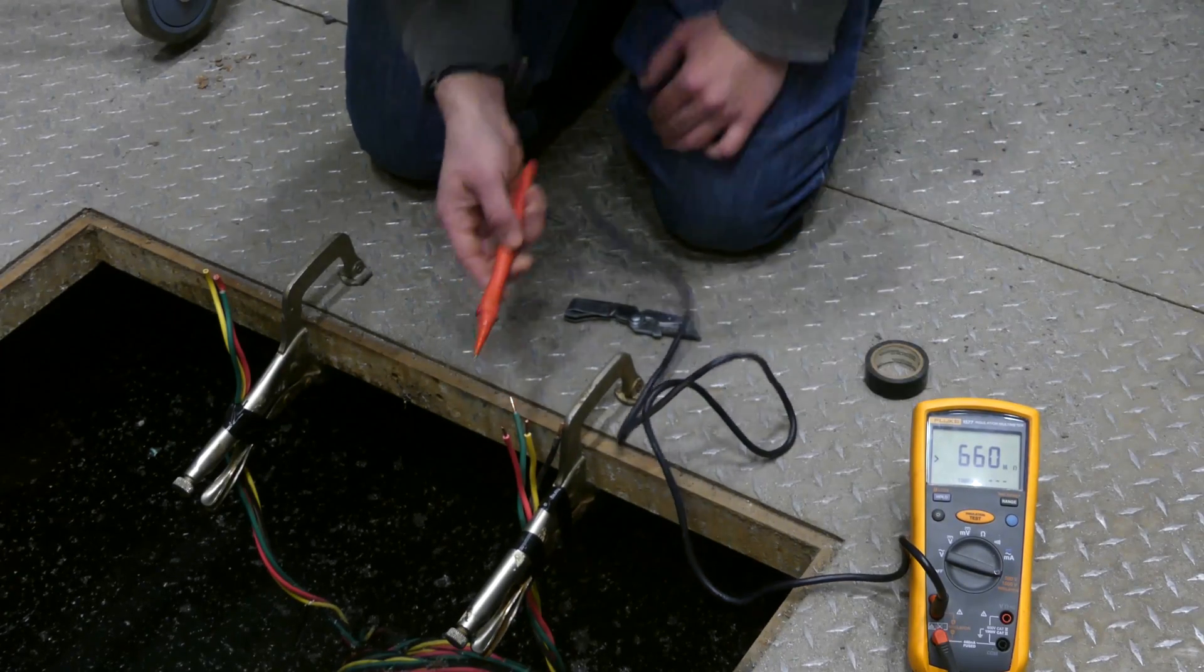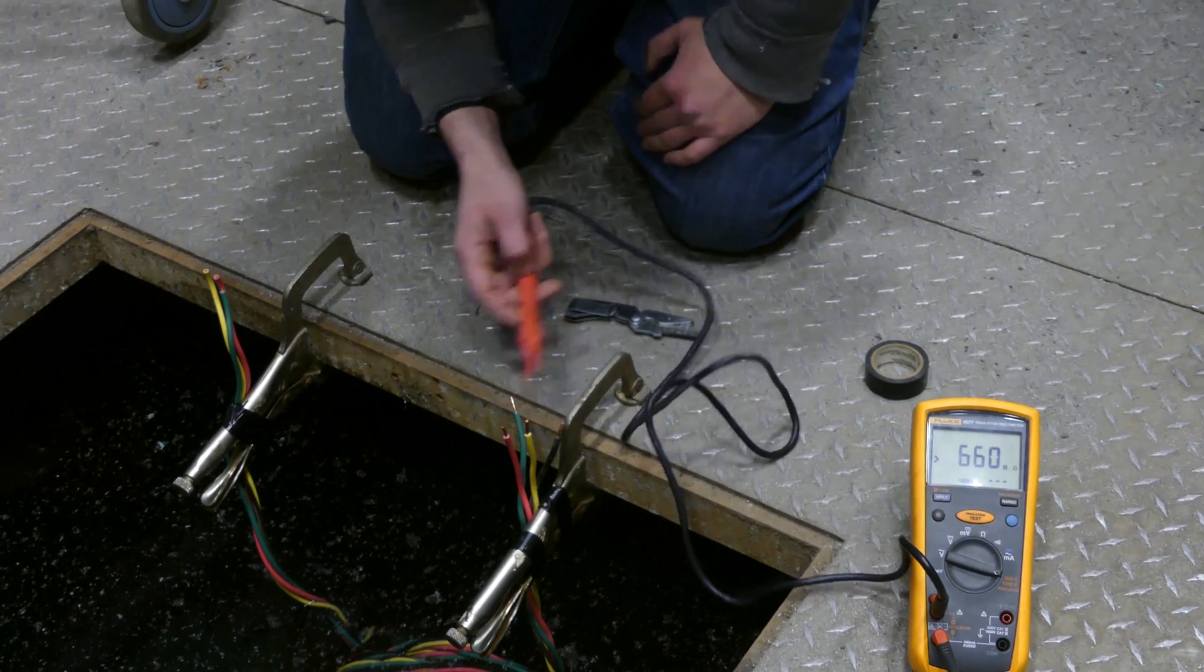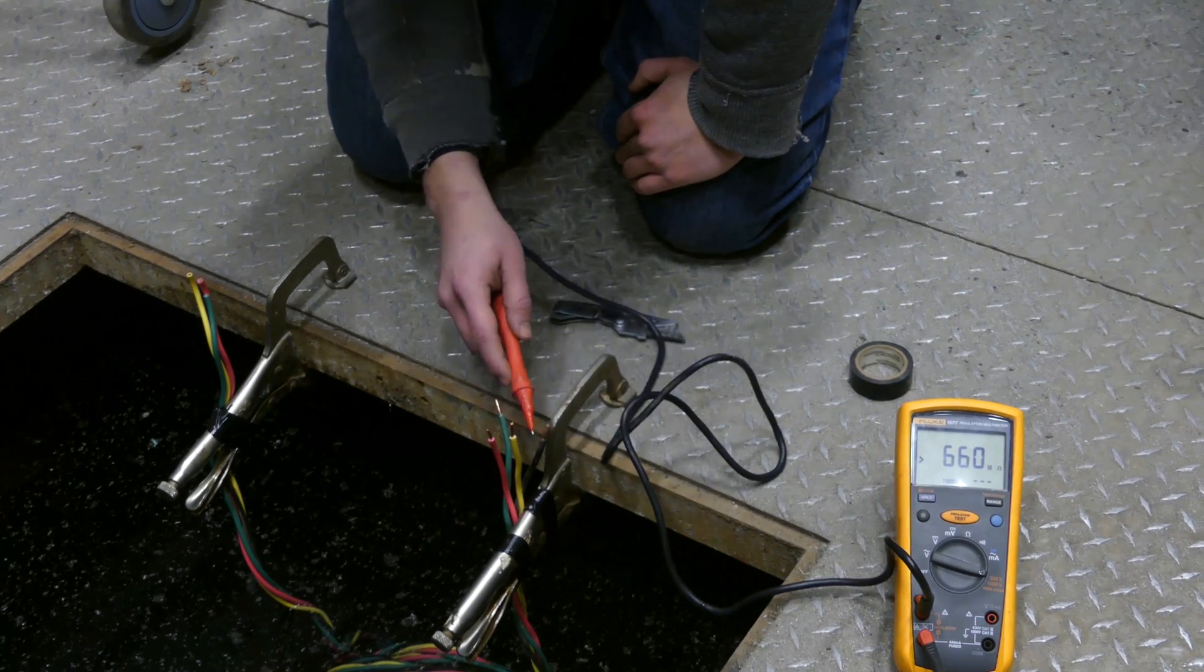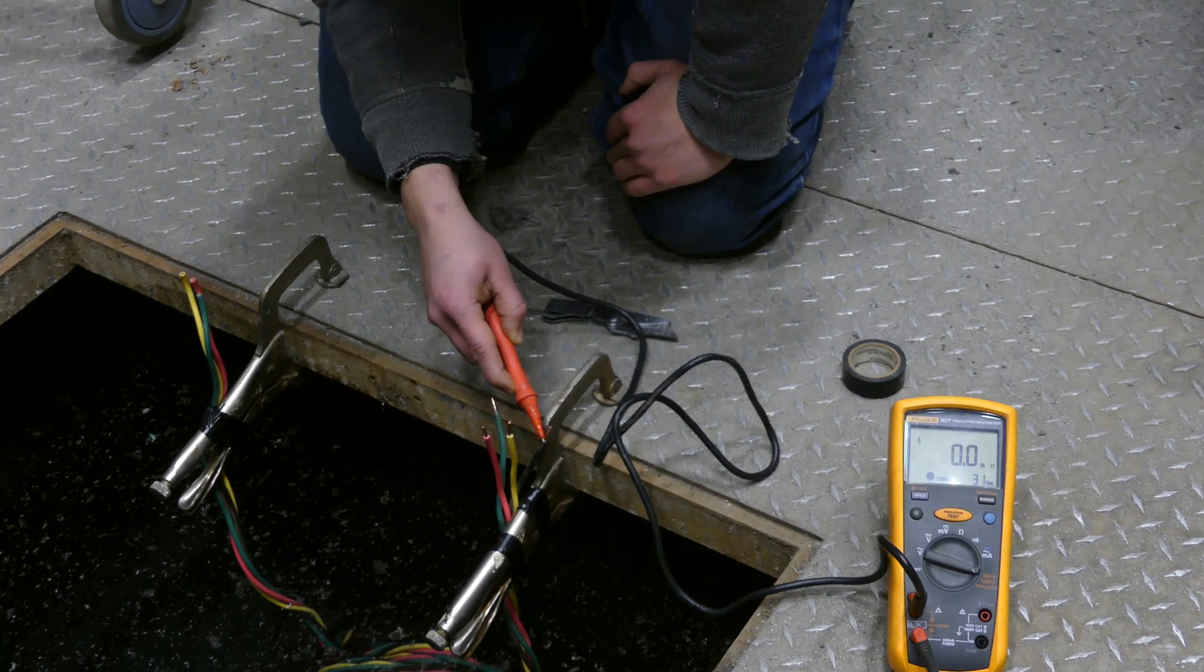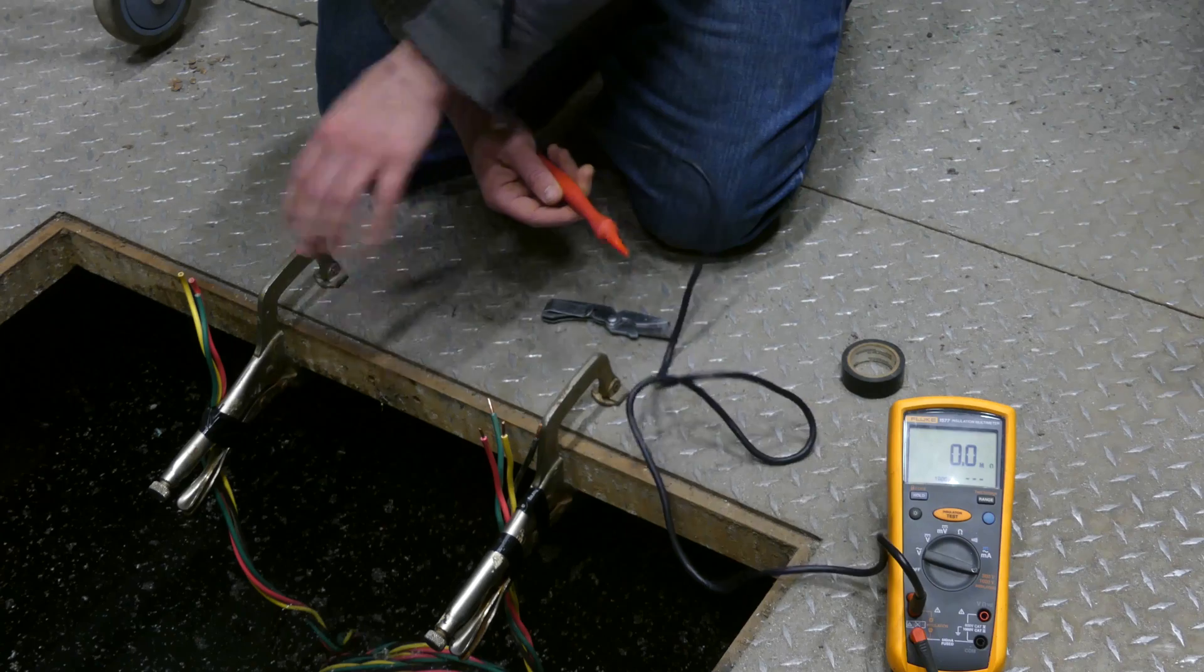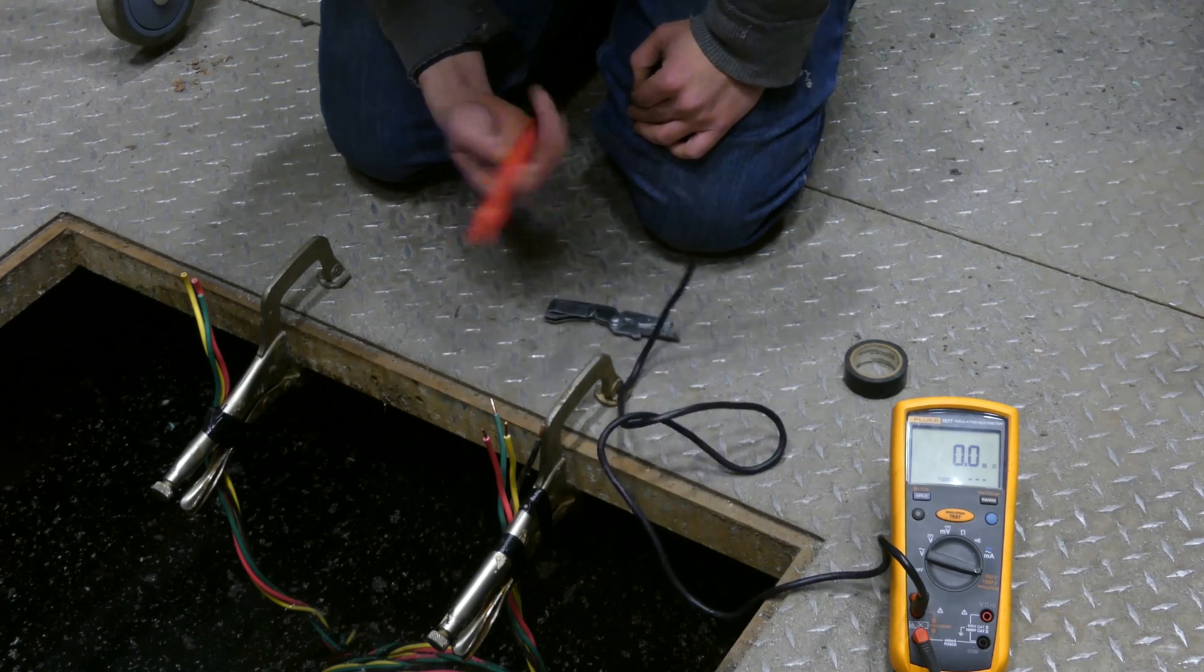So we're getting the 660 again. And the 660 on this meter I just learned is actually the max. It's infinity basically. It doesn't go any higher than that. So we could potentially be way higher than that, but we just wouldn't be able to see it on this meter. So let's test this black one. And wouldn't you know it, we're getting a zero. Now the incision that I made, we'll pull this out of the water and I'll show you the cut that I made was very small. However, it was able to pick it up immediately. So you can see the value of being able to test the wire.